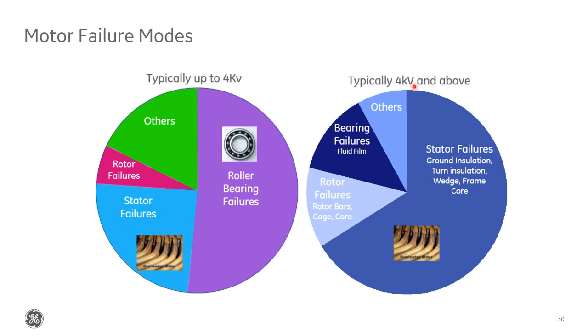Above 4 kV, stator failures make up a big chunk, but here we're also talking about issues with the foundation, with the core laminations, and the mechanical makeup in general. And again, you can see pretty decent chunks for the rotor and bearing failures that we traditionally are not detecting at all. So the question was, what can we do to account for some of these other failures in our relays?